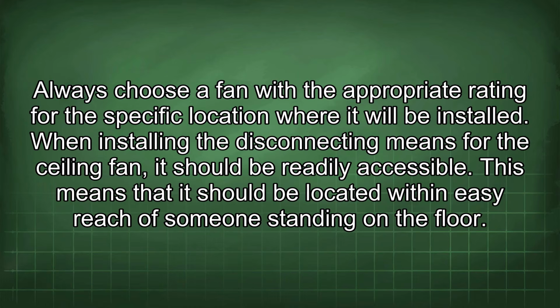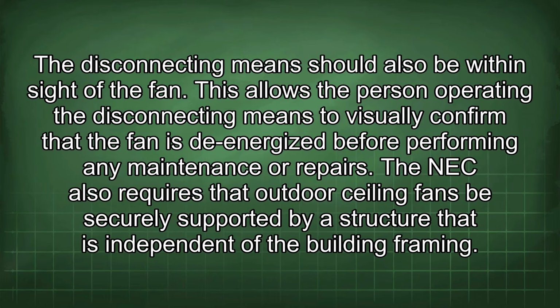When installing the disconnecting means for the ceiling fan, it should be readily accessible. This means that it should be located within easy reach of someone standing on the floor. The disconnecting means should also be within sight of the fan. This allows the person operating the disconnecting means to visually confirm that the fan is de-energized before performing any maintenance or repairs.